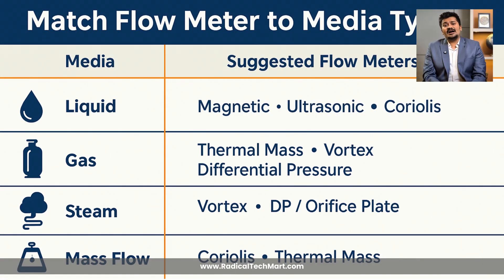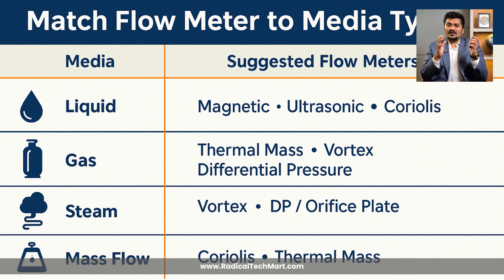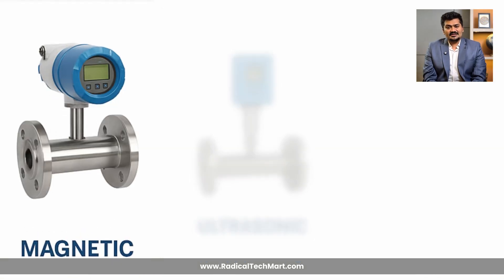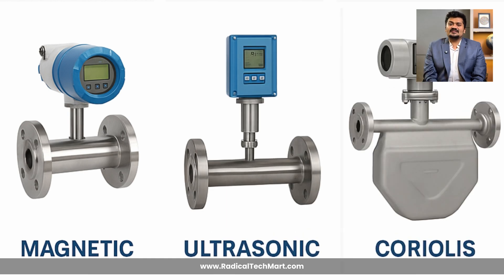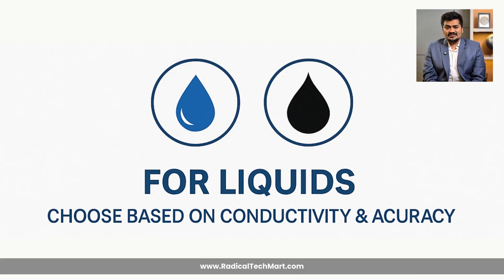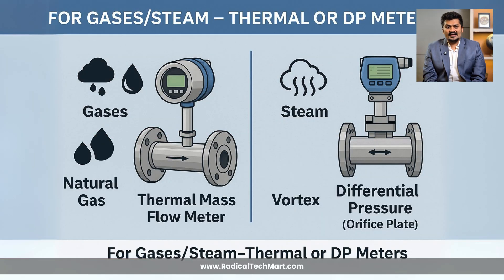The first thing you need to understand is your media — what exactly are you measuring. For liquids, consider magnetic, ultrasonic, or Coriolis flow meters depending on whether the liquid is conductive and how accurate your readings need to be. For gases, your options include thermal mass, vortex, or differential pressure flow meters.